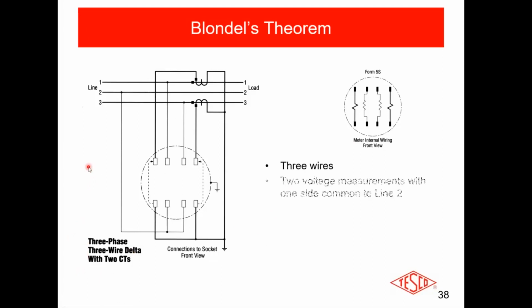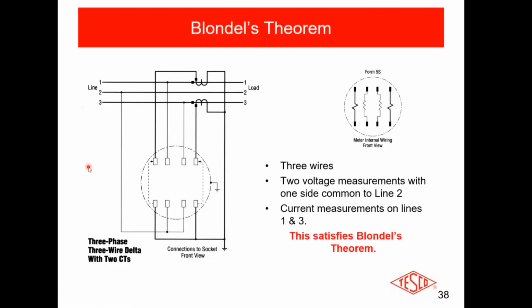All right? We got 3 wires, 2 voltage measurements with one side common to line 2, current measurements on lines 1 and 3. Does this meet Blondel's theorem? Yes, it does. We are good to go. So I just got a 5S system that I set up, and I set it up correctly, and it satisfies Blondel's theorem, which means this metering site will always give me correct energy measurements, providing that my site remains good. My meter remains good. My wires remain tight. I don't get broken wires. I don't have a lot of corrosion. This is going to give me good readings.